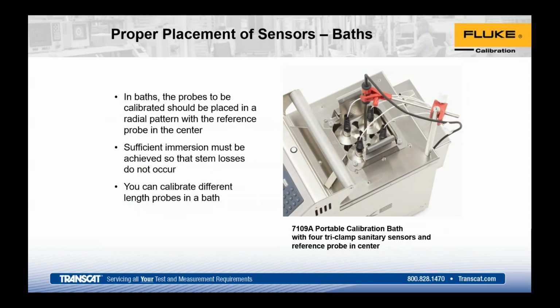So we had the first slide where I gave you that calibration example of the unit being calibrated in the dry well just to the display. We showed the placement there of the internal sensor and the unit being tested. The idea is getting your sensors closely aligned so you get a good reading, because otherwise the uniformity of the bath is going to be lessened. If you think of bath uniformity, that's taking the whole volume of the bath and saying, if I have a sensor in the top right, bottom left, and one in the middle, there's going to be this air gap. There's a way to reduce that by pushing everything close together within the same space and putting your reference there in the center. That gives you a better way to reduce the uncertainty of the top, bottom, middle placement that's done in the R&D side and the specification of the bath. So it can actually improve that uncertainty spec quite a bit.